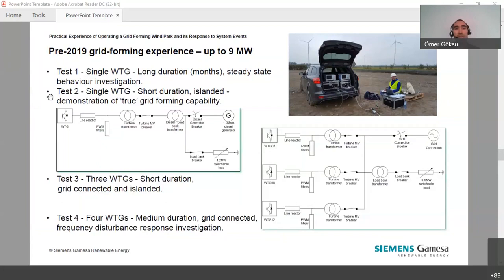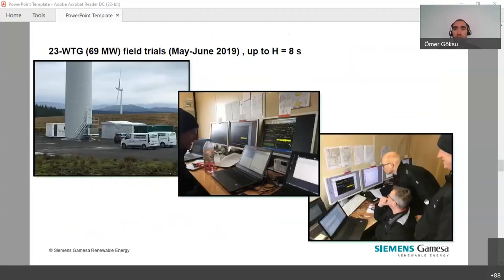After that, in the second stage, it was again a single turbine in islanded operation with grid forming function. You can see here it was started with a diesel and then left with a load. Then a three turbine topology was tested in a similar condition, again with grid connected and islanding modes. And then four turbines for a medium duration, and there were some disturbances. These were the startups before 2019.